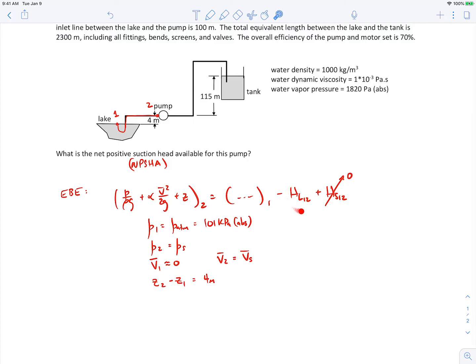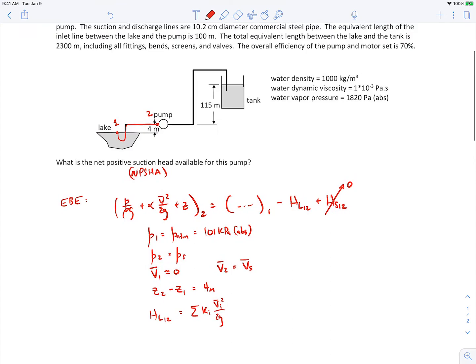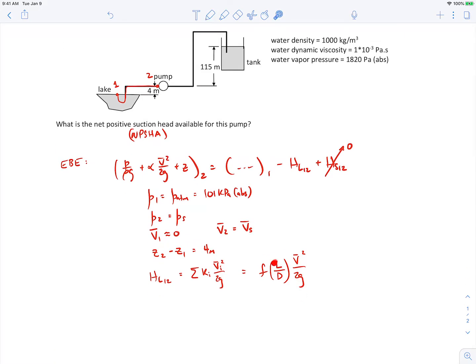We need to find the head loss between those two points. The head loss will be the sum of all minor loss coefficients times velocity head values. Since the equivalent length of the inlet line between the lake and the pump is 100 meters, we don't need to factor in minor losses explicitly — they're already embedded in the major loss using equivalent length. So head loss equals f times L over D times V-bar squared over 2g, where L is our equivalent length of 100 meters.